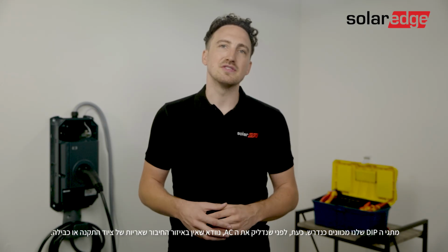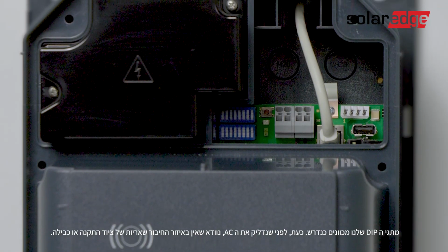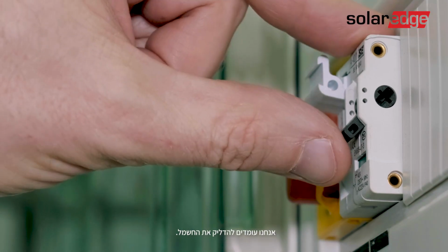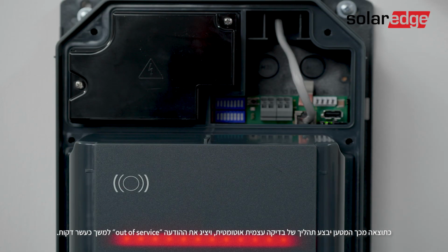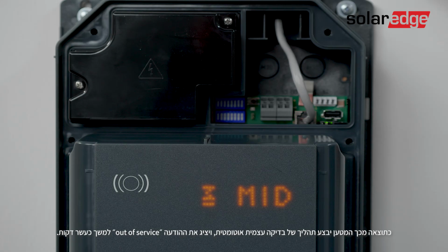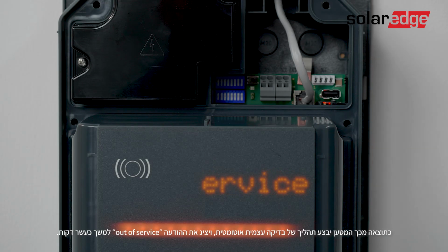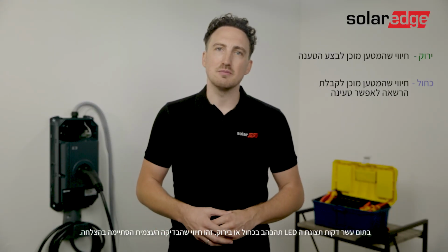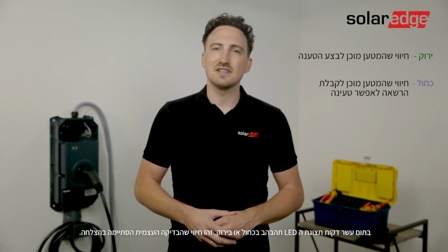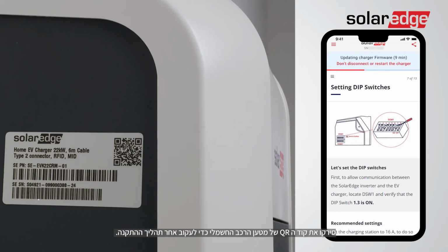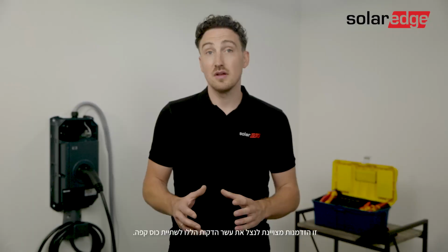Now, before we turn on the AC, we want to make sure that we don't have any residual installation or connection materials around the connection area. And we're going to make sure that the cables, the screw connections are properly locked in place. Alright, we're going to move on to turning on the electrical grid. Now what's going to happen is the charger will start an automatic self-test procedure and will display out of service for approximately 10 minutes. After the 10 minutes, the LED bar should flash blue or green. This indicates that the self-test was successful. Scan the EV charger QR code to monitor the installation process. Meanwhile, you can use those 10 minutes to enjoy a cup of coffee.